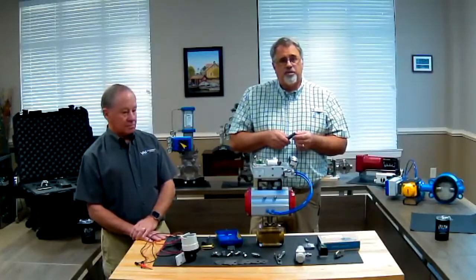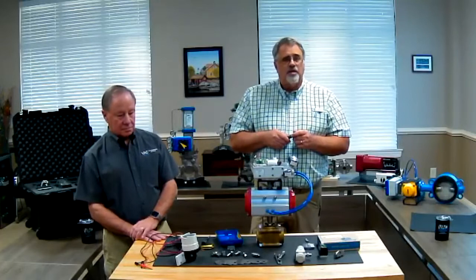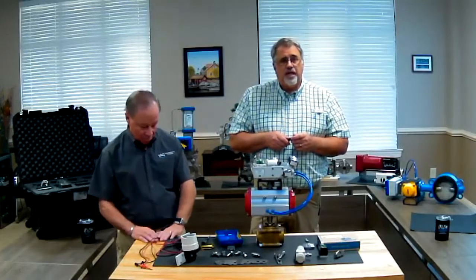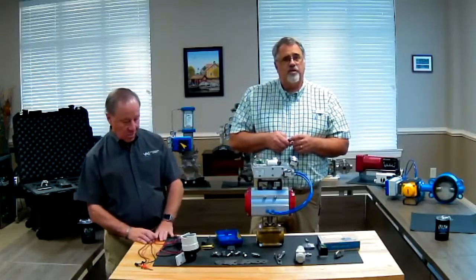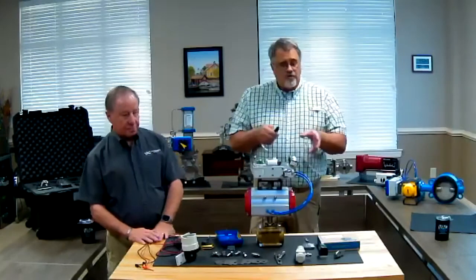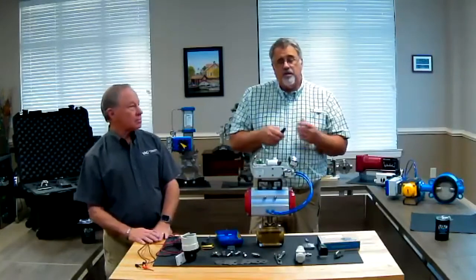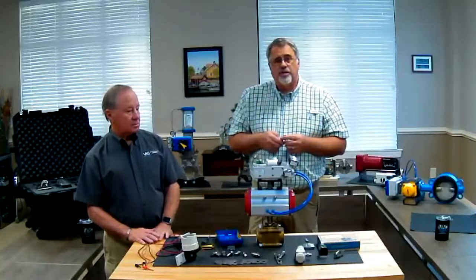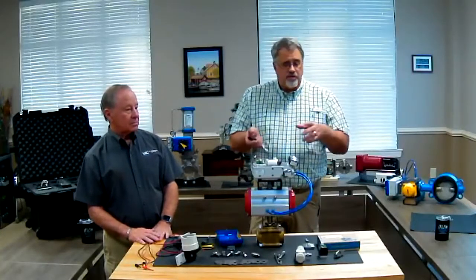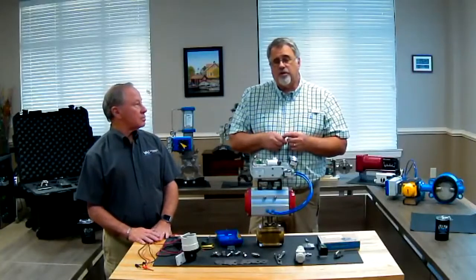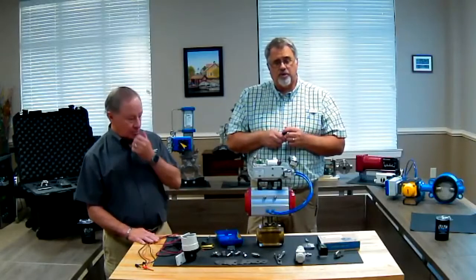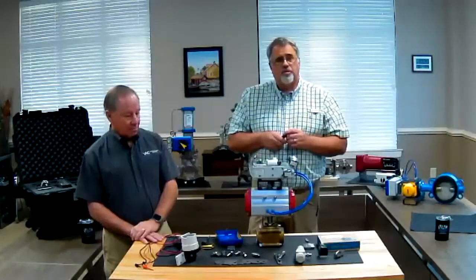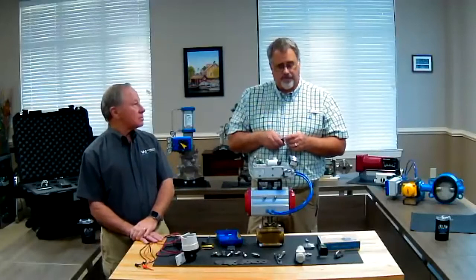Complete replacement of the positioner by the time you do all of the other things can typically take 90 minutes or more, especially if you're in a difficult location. When you do replace a pilot valve or an I to P, you don't have to completely recalibrate the positioner either. If you're installing one from scratch, you have to start calibration from scratch. But if you're just replacing those components, typically you can just double check your zero and be back up and running.